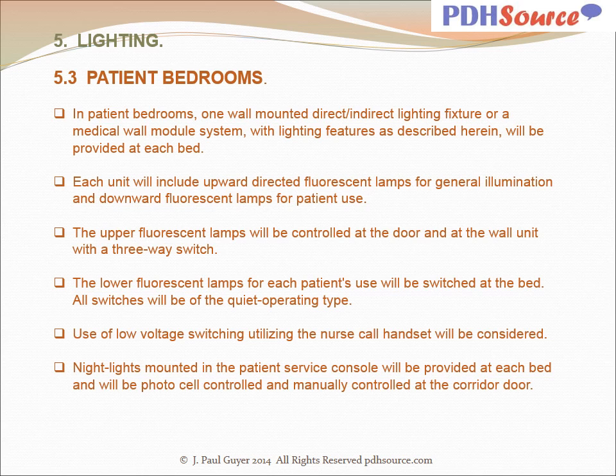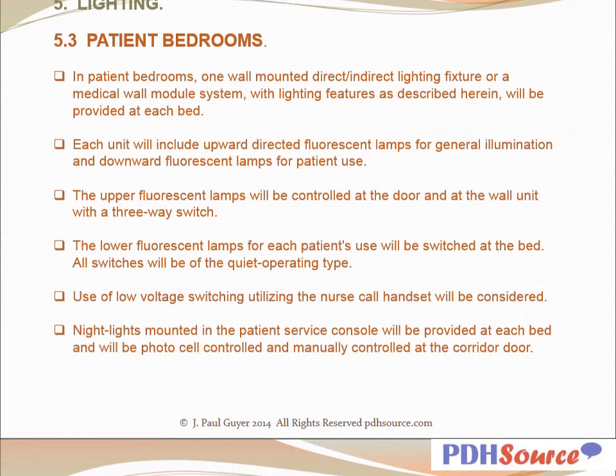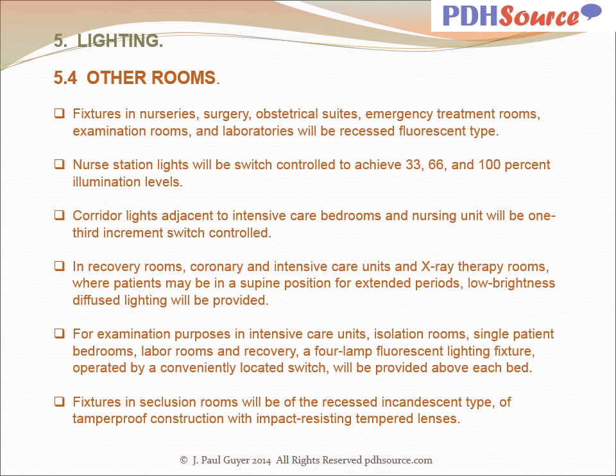All switches will be of the quiet operating type. Use of low voltage switching utilizing the nurse call handset will be considered. Night lights mounted in the patient service console will be provided at each bed and will be photocell controlled and manually controlled at the corridor door. Fixtures in nurseries, surgery, obstetrical suites, emergency treatment rooms, examination rooms, and laboratories will be recessed fluorescent type.